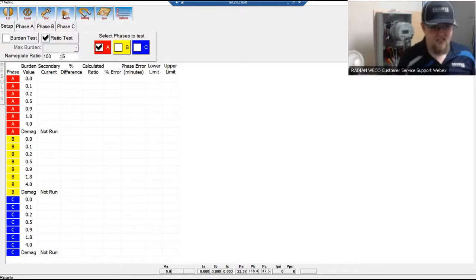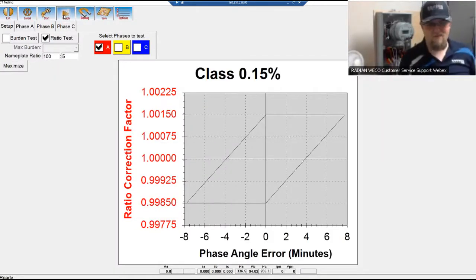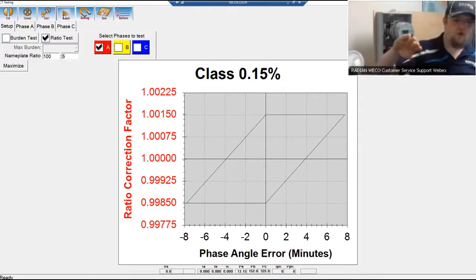When you open up CT testing, this is the window that you'll be greeted with. It gives you bits and pieces of everything. At the top here, we have the exit button, which exits back out to the menu I was just in. Cancel stops the test that's currently running. Start starts the test that you set up in this window. Graph shows a parallelogram of the test that you ran. Right now I haven't run any tests yet on the CT, so there's nothing to show, but it'll show the parallelogram graph and a curve for if you're adding excess burden and show where the secondary currents lie based on that.